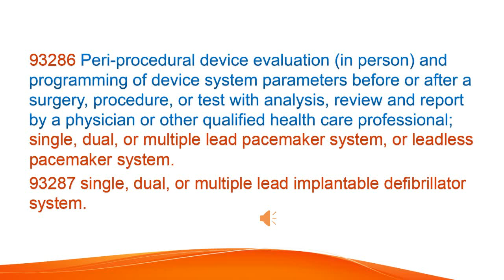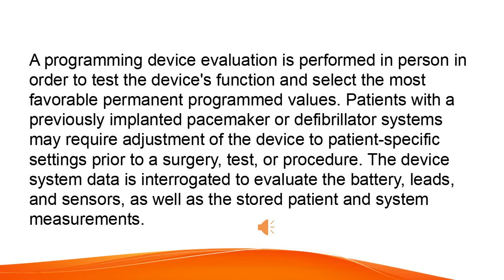A programming device evaluation is performed in person in order to test the device's function and select the most favorable permanent programmed values. Patients with a previously implanted pacemaker or defibrillator systems may require adjustment of the device to patient-specific settings prior to a surgery, test, or procedure. The device system data is interrogated to evaluate the battery, leads, and sensors, as well as the stored patient and system measurements. If necessary, the device is programmed to settings appropriate for the surgery, test, or procedure. A post-procedure evaluation and programming may also be performed, with adjustments as required.